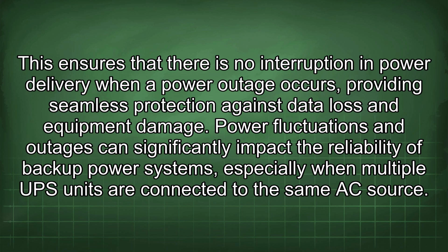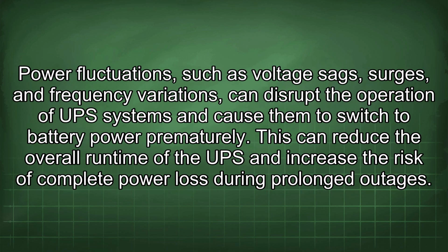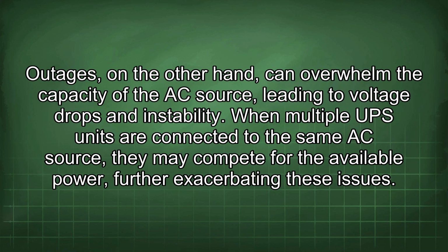Power fluctuations and outages can significantly impact the reliability of backup power systems, especially when multiple UPS units are connected to the same AC source. Power fluctuations, such as voltage sags, surges, and frequency variations, can disrupt the operation of UPS systems and cause them to switch to battery power prematurely. This can reduce the overall runtime of the UPS and increase the risk of complete power loss during prolonged outages. Outages, on the other hand, can overwhelm the capacity of the AC source, leading to voltage drops and instability. When multiple UPS units are connected to the same AC source, they may compete for the available power, further exacerbating these issues.